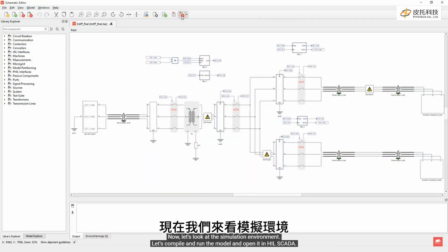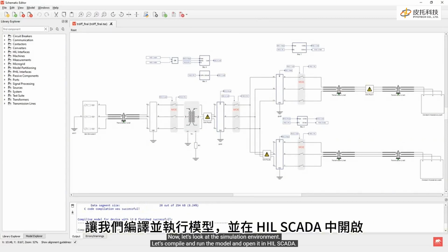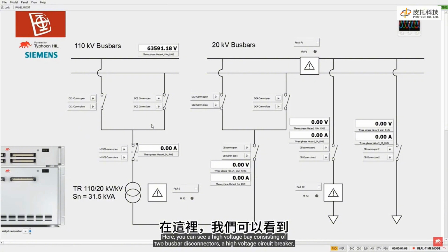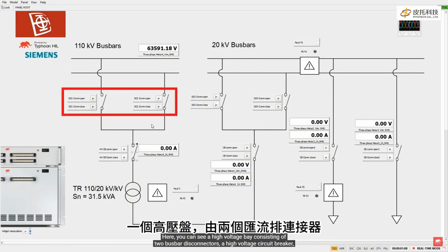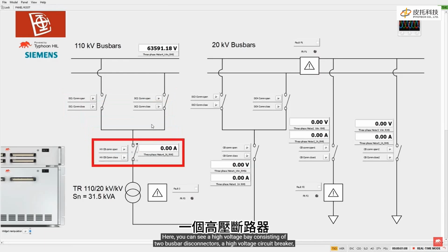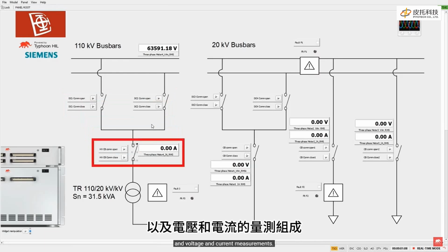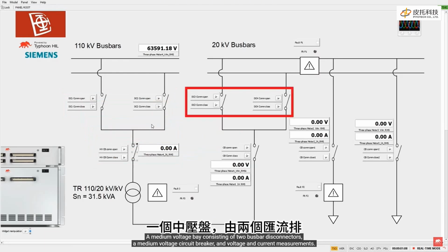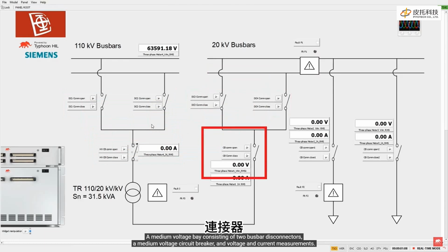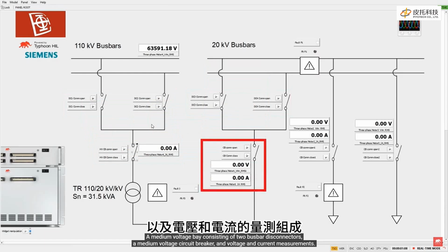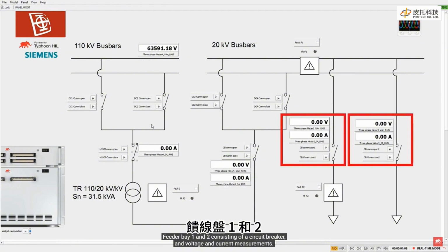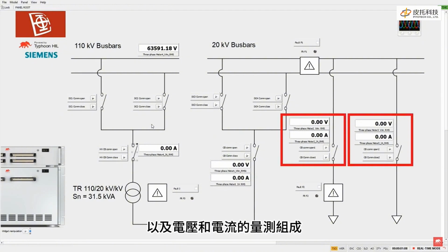Now let's look at the simulation environment. Let's compile and run the model and open it in HIL SCADA. Here we can see a high voltage bay consisting of 2 bus bar disconnectors, a high voltage circuit breaker, and voltage and current measurements. A medium voltage bay consisting of 2 bus bar disconnectors, a medium voltage circuit breaker, and voltage and current measurements. Feeder bays 1 and 2 consisting of a circuit breaker and voltage and current measurements.